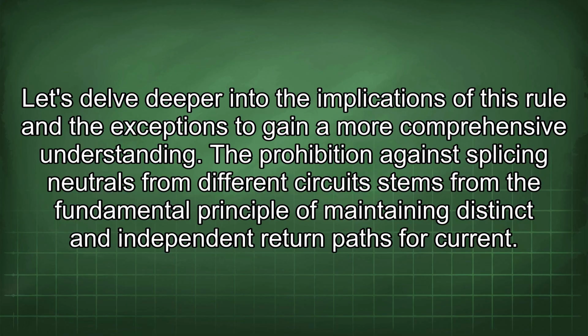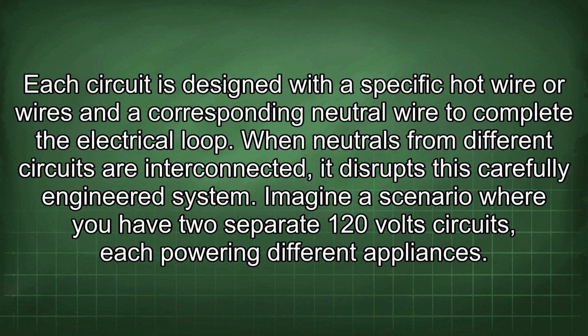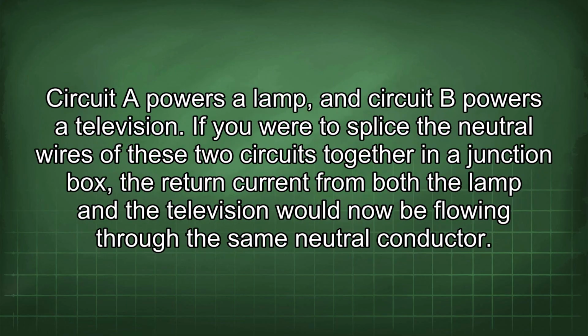The prohibition against splicing neutrals from different circuits stems from the fundamental principle of maintaining distinct and independent return paths for current. Each circuit is designed with a specific hot wire or wires and a corresponding neutral wire to complete the electrical loop. When neutrals from different circuits are interconnected, it disrupts this carefully engineered system. Imagine a scenario where you have two separate 120-volt circuits, each powering different appliances. Circuit A powers a lamp and Circuit B powers a television. If you were to splice the neutral wires of these two circuits together in a junction box, the return current from both the lamp and the television would now be flowing through the same neutral conductor.